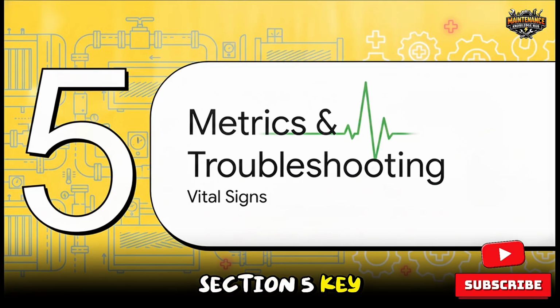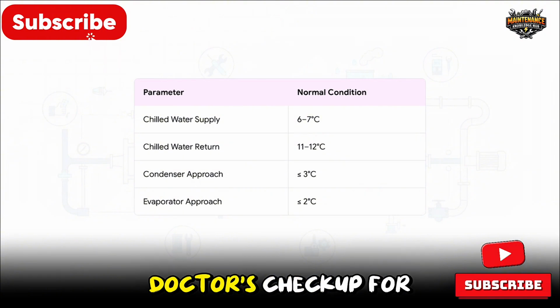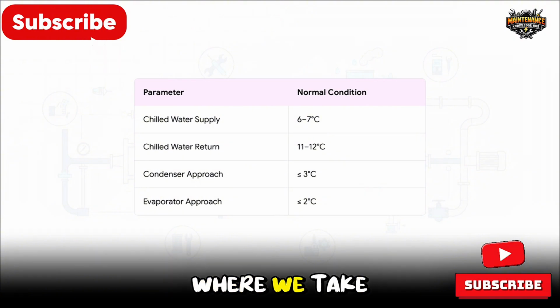Section 5. Key metrics and troubleshooting. Think of this phase as the doctor's checkup for the chiller, where we take a close look at the vital signs. These key performance indicators are your ultimate scorecard. We want our chilled water supply temperature leaving the machine to sit between 6 and 7 degrees Celsius. We expect the return temperature coming back from the building to be between 11 and 12 degrees.